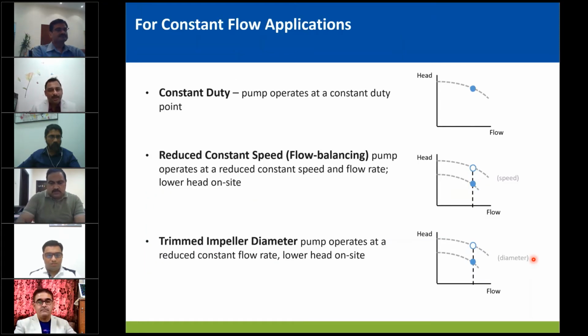Now, talking about constant flow applications, traditionally we used to have the duty point selected for a fixed impeller. You will have the flow and head selected. The x-axis is flow, y is head, and the dot is where you have selected, and that dotted line is the impeller line. So you're supposed to operate here, and if anything changes in the system, for example, it's operating on a lower head, it would be pumping more flow and it will overload the motor.